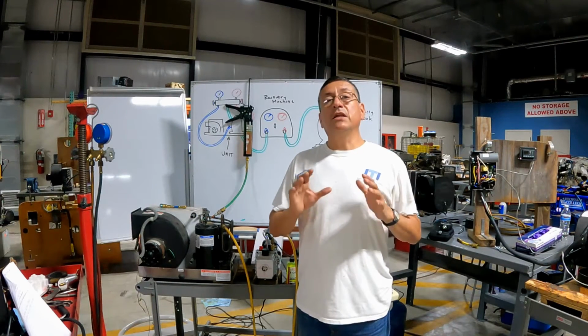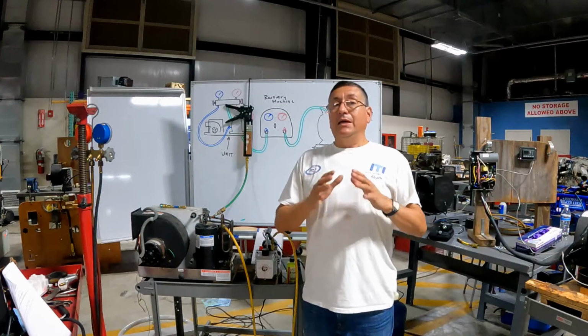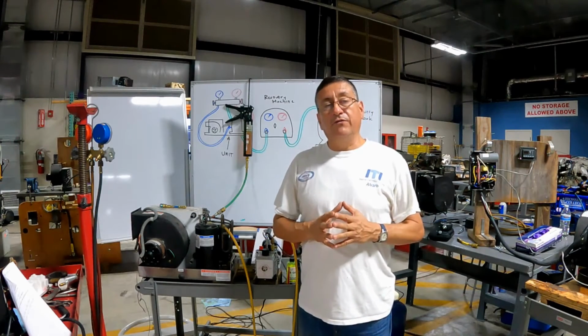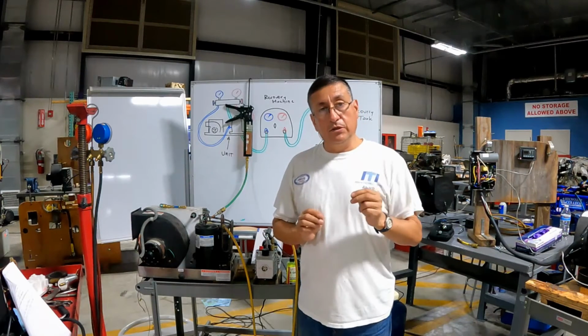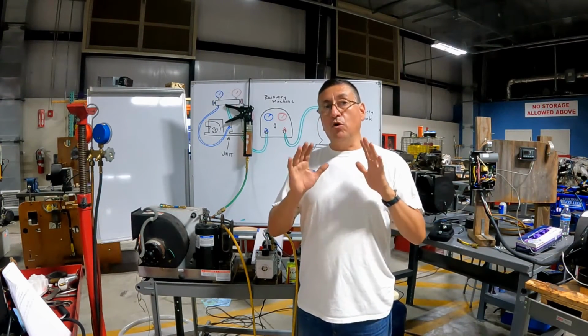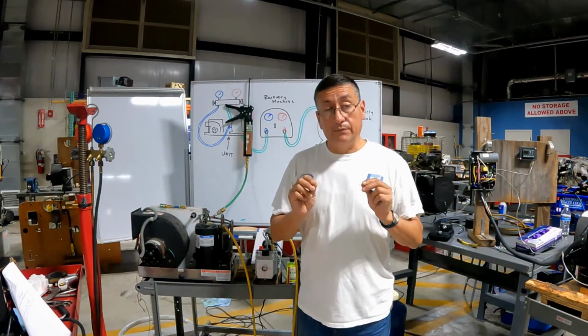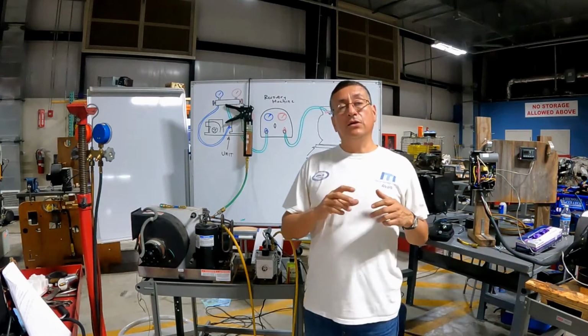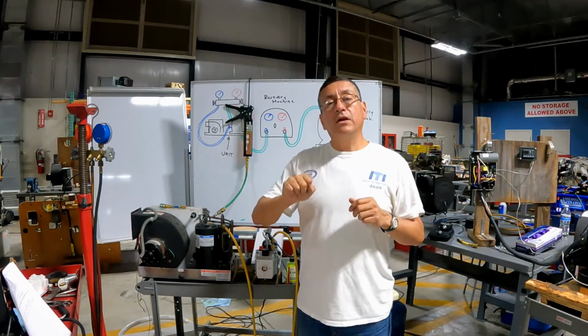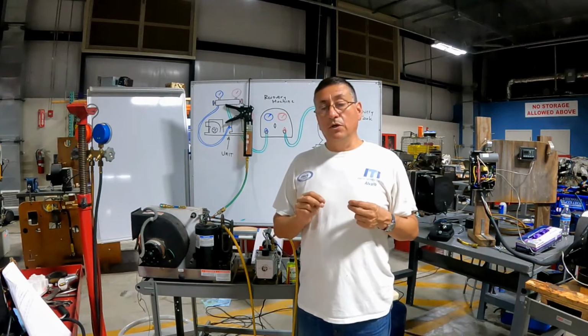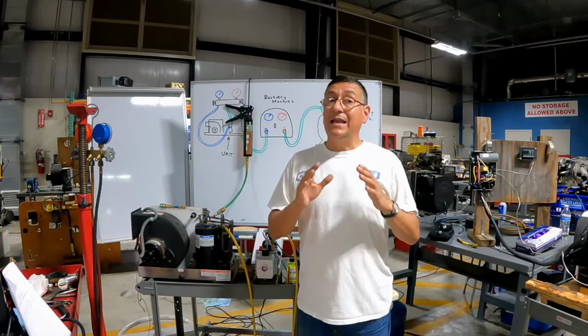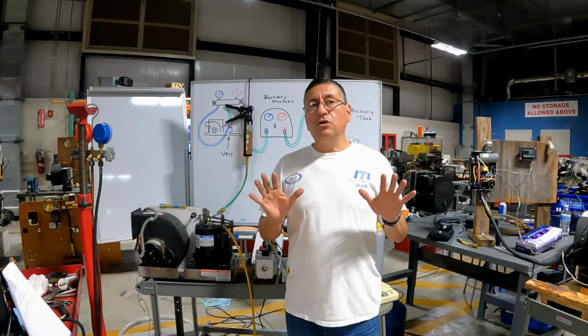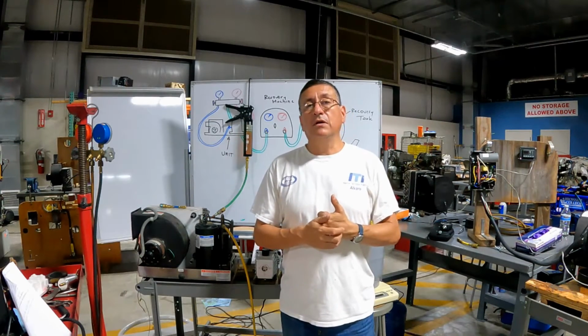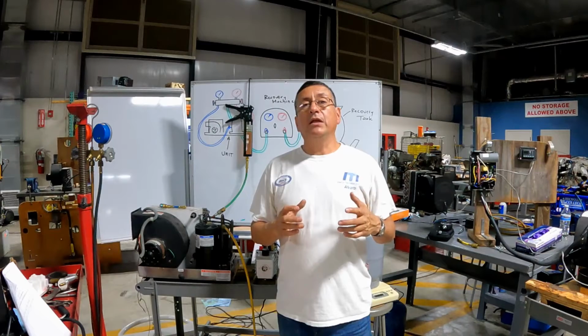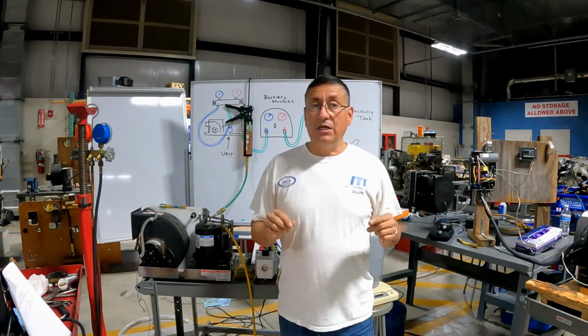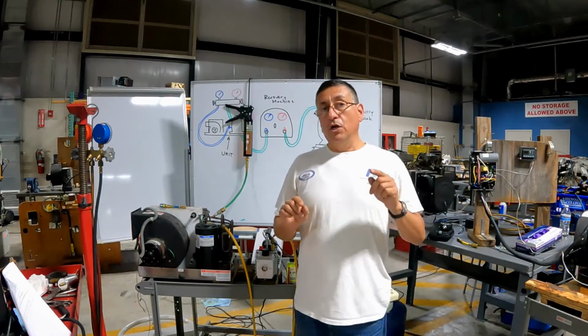Vacuuming the system is an important process because you need to eliminate moisture. Moisture is the enemy of the refrigerant, and you need to eliminate solid particles, contaminants. The enemy is moisture and solid particles and air. For that reason, as soon as you cut the lines and you separate the lines, the first step is to cover the lines in order to avoid the intrusion of particles, the intrusion of humidity and nitrogen. Okay. In marine application, soldering is not recommended. In some cases, if you want to solder, I recommend soldering while introducing dry nitrogen in the lines in order to avoid the formation of cupric oxide.